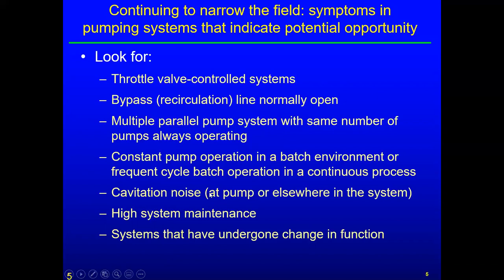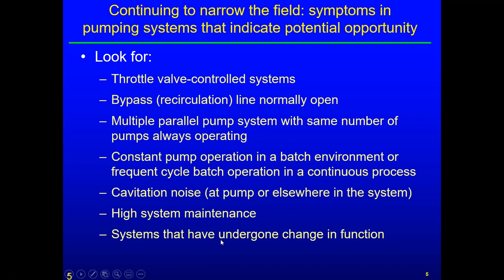Cavitation occurs when pressure in the system goes to or below vapor pressure, essentially boiling the fluid. Vapor bubbles form, pass through a pump or valve, and cause damage — it'll tear up the pump and the valve. High maintenance costs are an indication to investigate. Also, if you've undergone a change of function — for example, removing a line that required a lot of flow without changing the pump — you may be operating far off the pump's design point. These are all possible symptoms of an inefficient pumping system.